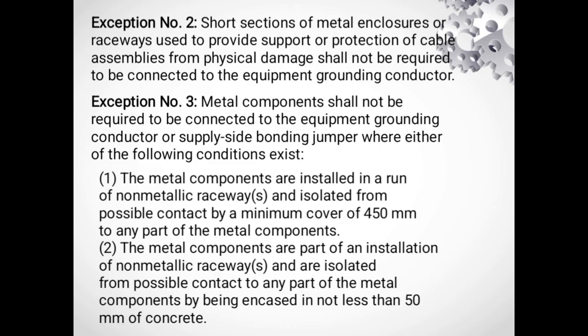Exception number 2, short sections of metal enclosure or raceway used to provide support or protection of cable assemblies from physical damage shall not be required to be connected to the equipment grounding conductor. Exception number 3, metal components shall not be required to be connected to the equipment grounding conductor or supply side bonding jumper where either of the following conditions exist. Number 1, the metal components are installed in a run of a non-metallic raceway and isolated from possible contact by a minimum cover of 450 mm to any part of the metal components. Number 2, the metal components are part of an installation of non-metallic raceways and are isolated from possible contact to any part of metal components by being encased in not less than 50 mm of concrete.